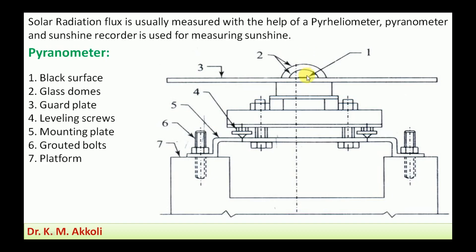If both beam radiation as well as diffuse radiation fall on the instrument, then that is the global radiation we are going to measure. For measuring global radiation, the shading ring is not provided. If measuring only diffuse radiation, a shading ring is provided which shades the black surface — typically a thermopile — so it receives only diffuse radiation, not direct radiation.